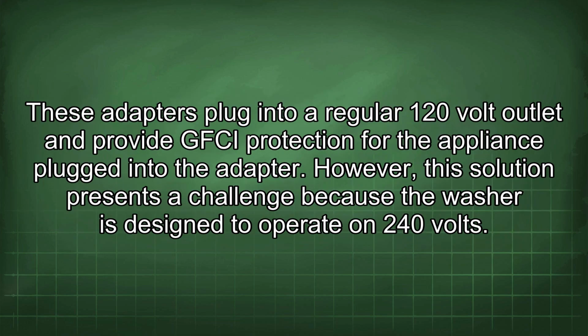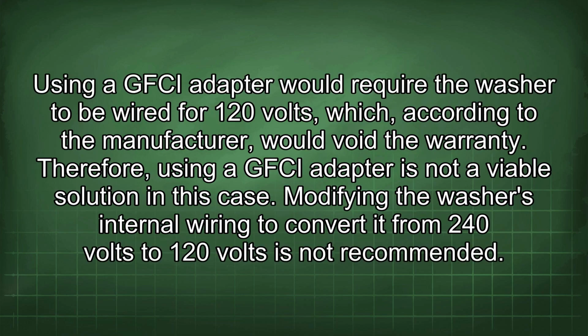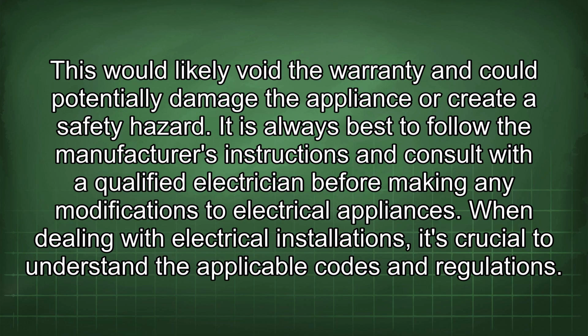These adapters plug into a regular 120 volt outlet and provide GFCI protection for the appliance plugged into the adapter. However, this solution presents a challenge because the washer is designed to operate on 240 volts. Using a GFCI adapter would require the washer to be wired for 120 volts, which, according to the manufacturer, would void the warranty. Therefore, using a GFCI adapter is not a viable solution in this case. Modifying the washer's internal wiring to convert it from 240 volts to 120 volts is not recommended. This would likely void the warranty and could potentially damage the appliance or create a safety hazard.